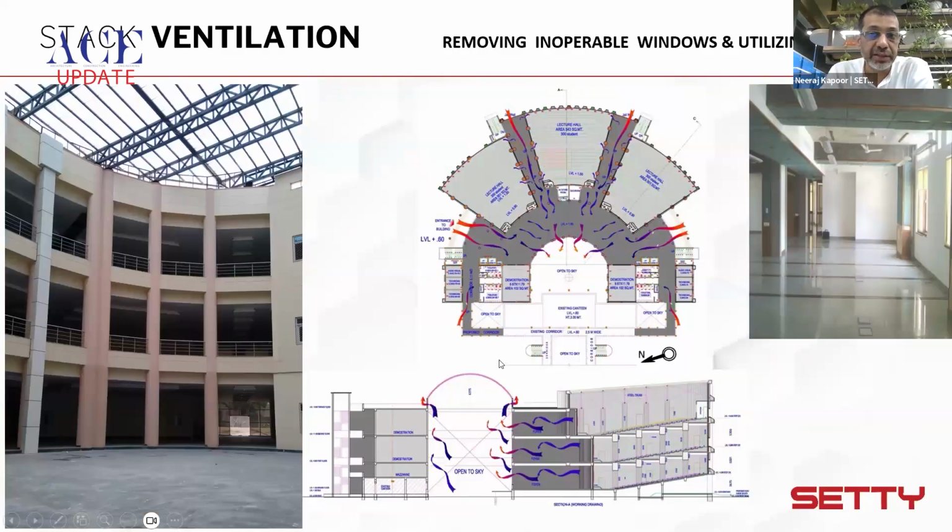This particular building again is utilizing a different kind of natural ventilation. We broke open the windows in some cases, and in certain other cases we introduced jali, which facilitated natural ventilation from the outside. Because it was a tall space with an atrium in the middle, this allowed the air to gently keep rising as it picked up heat. This is another project, not this particular one, where we are using the same stack effect or displacement ventilation in an indoor environment.